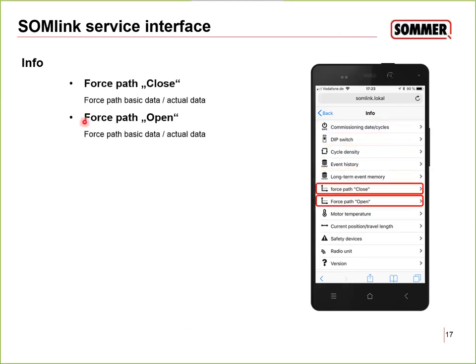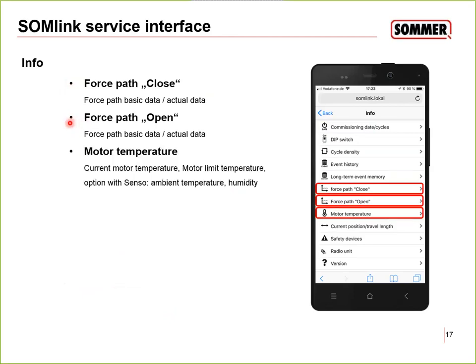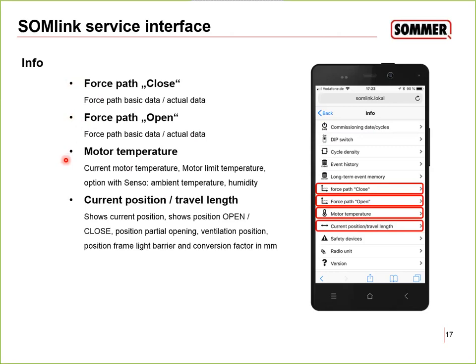Next is force paths open and force paths closed. So here you can view yourself the force path. So how is it looking, on which point of the door does the operator need more force or less force? You can view this in a graphic on the display of your smartphone. Next point is the motor temperature, so you can see the actual current motor temperature. The current position, the travel length is possible to read here. So where does the motor in a moment have the position, on which position.